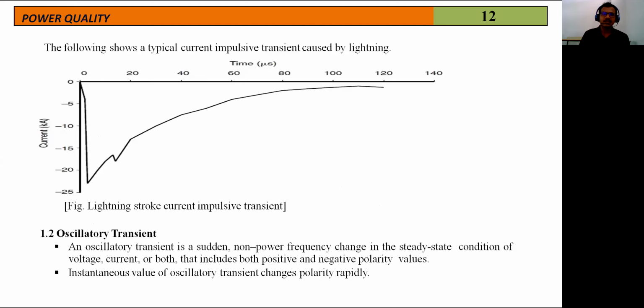Second, if you see the example, the following shows a typical current impulsive transient caused by lightning. When lightning falls on a power line, this is the waveform of the current caused by the lightning transient. If you observe clearly, at 0 microseconds, suddenly the transient occurred, lightning occurred. Suddenly there is a drastic change in the magnitude of the current, from 0 to minus 23 kilo amperes. That means it is in the negative polarity, 23 kilo amperes, a sudden increase.